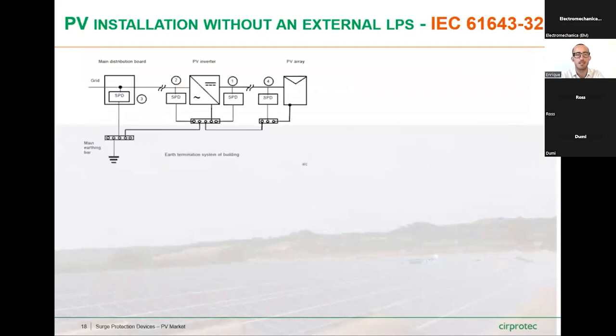Now, we will check together each of these three types of PV installations according to the IEC and how they should be properly protected in front of surges according with the standards. Let's start with the PV installation without an external LPS in place, without a lightning rod in place. Here, you see a drawing showing the PV array, the PV inverter, and the main distribution board with the different earthing systems in place.